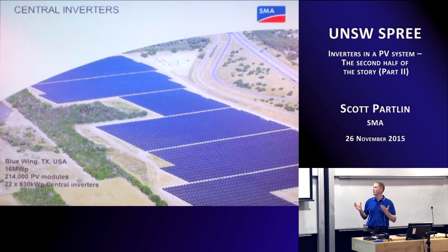So that's probably the main point about where central inverters have their place: when the systems start to get very large, so utility scale or sub-utility scale. Anything that's not connected to the low voltage network typically and is large, central inverter. So that's an example of a plant in the US, 16 megawatts, 214,000 PV modules and 22 central inverters. So if they were string inverters, there would be at least 400. And if they were microinverters, there'd be 214,000.